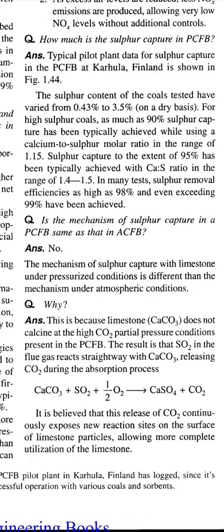The result is that SO₂ in the flue gas reacts directly with calcium carbonate, releasing carbon dioxide during the absorption process: CaCO₃ + SO₂ + ½O₂ → CaSO₄ + CO₂. It is believed that this release of CO₂ continuously exposes new reaction sites on the surface of limestone particles, allowing more complete utilization of the limestone.